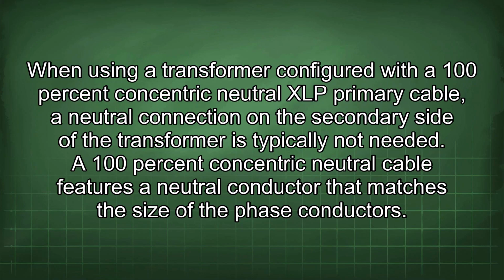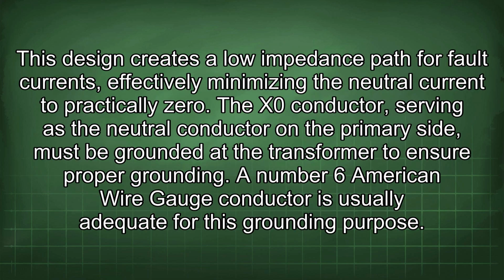When using a transformer configured with a 100% concentric neutral XLP primary cable, a neutral connection on the secondary side of the transformer is typically not needed. A 100% concentric neutral cable features a neutral conductor that matches the size of the phase conductors. This design creates a low impedance path for fault currents, effectively minimizing the neutral current to practically zero.